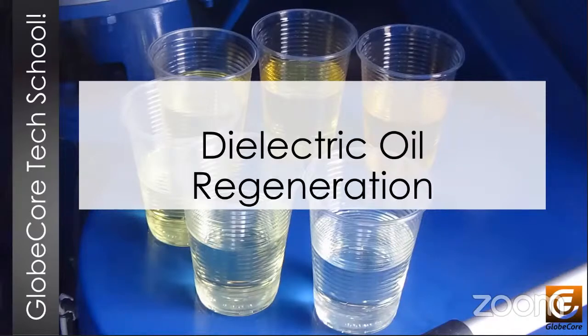So the regeneration of dielectric oil is not by any means a new process. It has been around for many years, and it's been in continuous development over these years. There are standards that include quality criteria now, and we're going to mention the IEC 60422 standard and the Mineral Oil Recovery Guide and criteria for its use, which is the IEEE C57.637, and that standard was introduced in 2015. So these standards will give us the necessary definitions and parameters, so we can learn a little bit more about these processes. Those processes will allow us to save a lot of oil through regeneration.